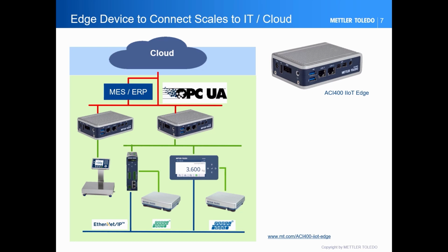The ACI 400 includes an OPC UA server with the companion specification for weighing. The solution with an additional edge device, as shown here, creates a win-win situation. For Mettler Toledo, it has the benefit that it allows us to connect the entire existing product range via OPC UA to the MES, ERP, cloud environment, while we have to maintain one device only.